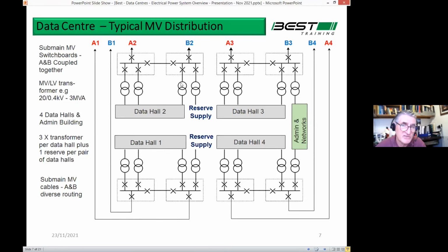So in this case, you have 3 transformers, so there's about 9 megawatts of capacity going in there, but the servers don't use all the power. If 9 megawatts is going in, probably around 6 to 7 megawatts would be used for processing data, and the remainder of the power is used to cool the plant, to cool down the servers. There are different ways of doing that. We're not going to talk about that today, but you can have air cooling, chilled water, refrigerant cooling. There are all different ways of doing it, and I cover that in the main data center course I do.